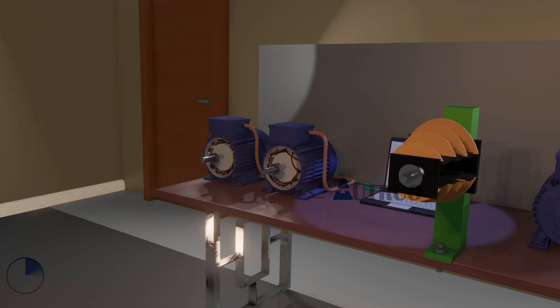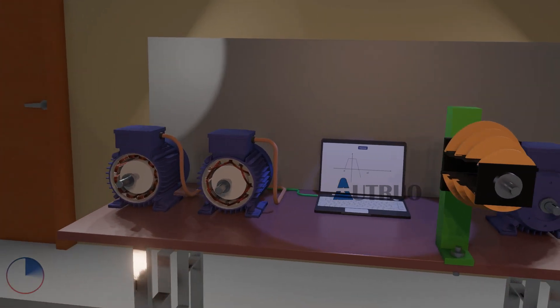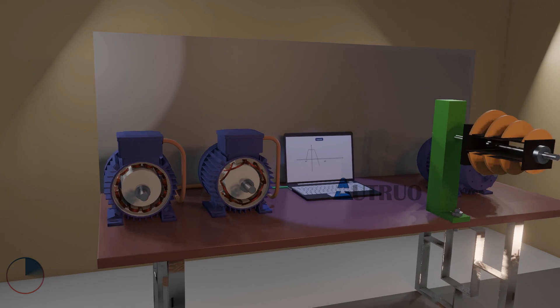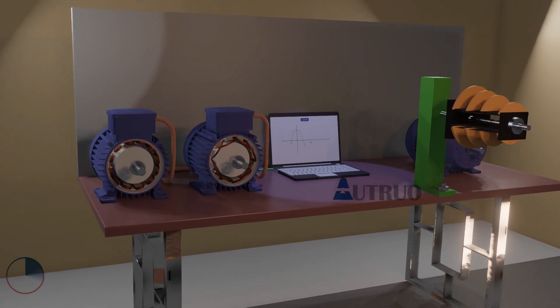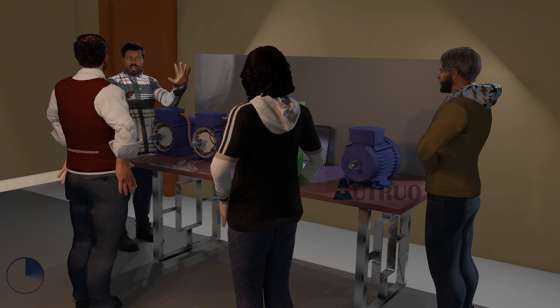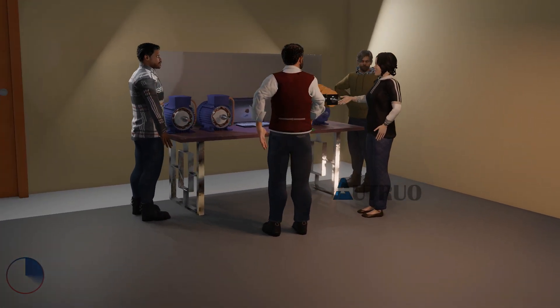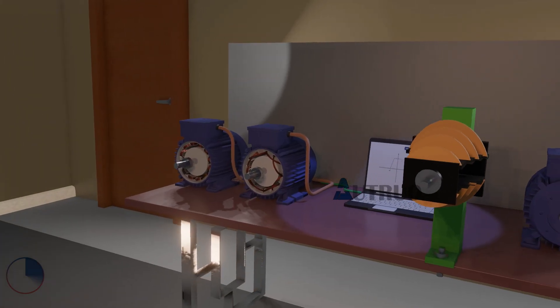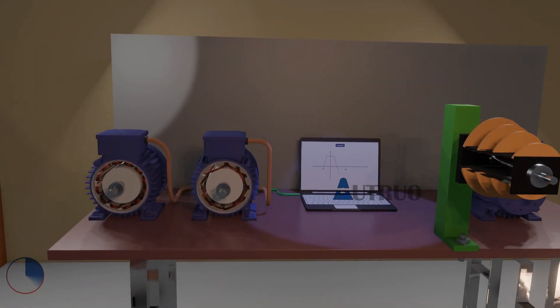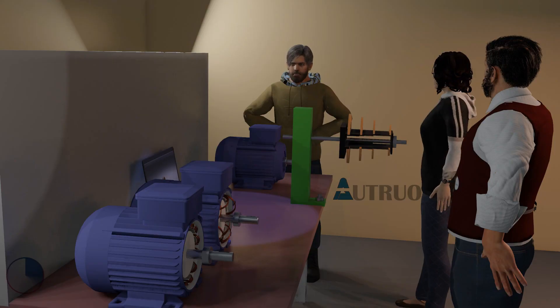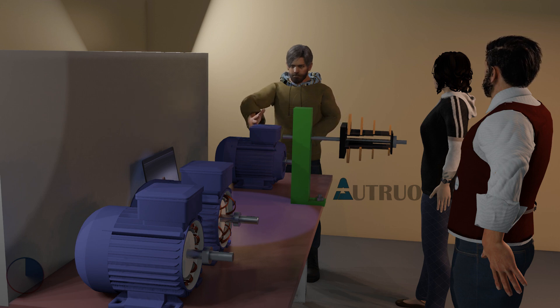With this design, a motor with concentrated winding tends to have less ohmic losses than a motor with distributed coils. During the coil winding process, the odds of making a mistake are very low because the start and end of the coil are wound on a single tooth. The wound coil can be visually seen at a distance, so the connections after winding will not be difficult.